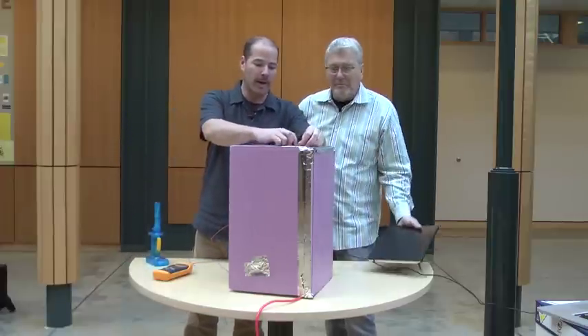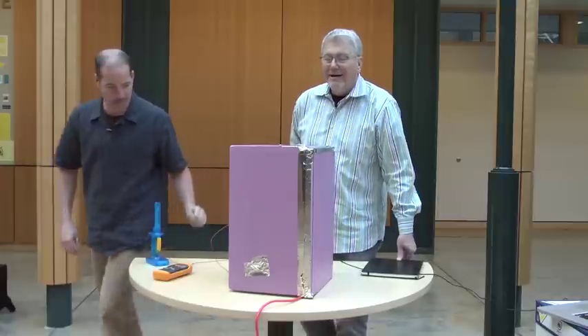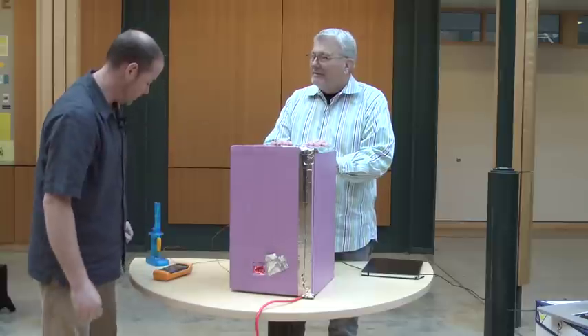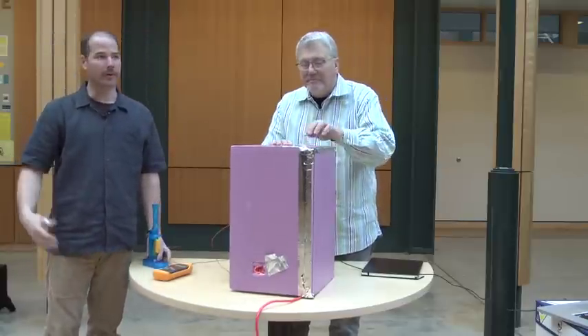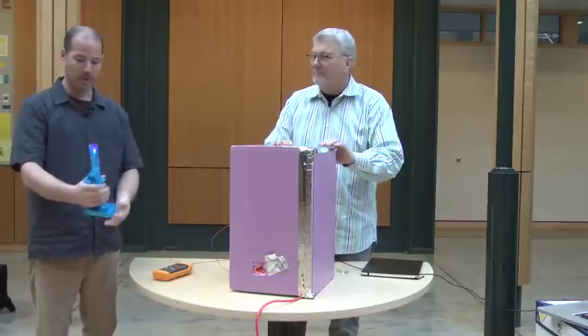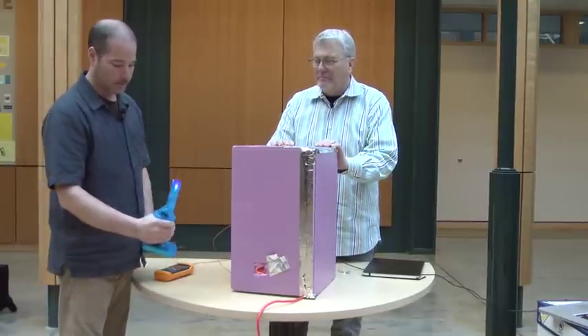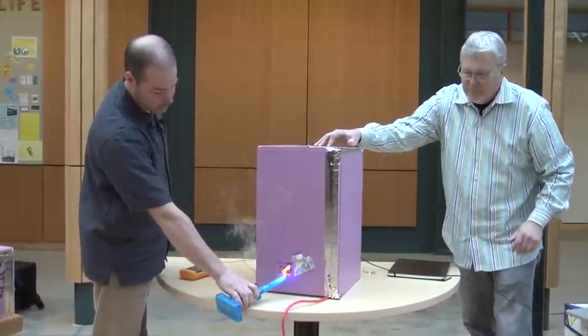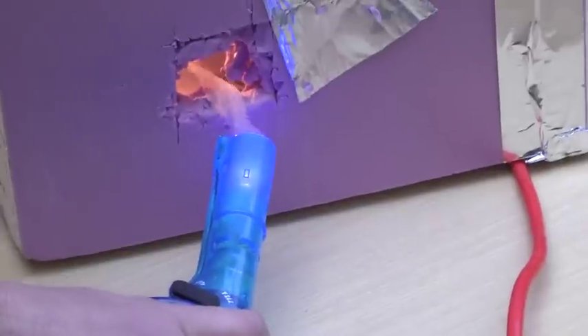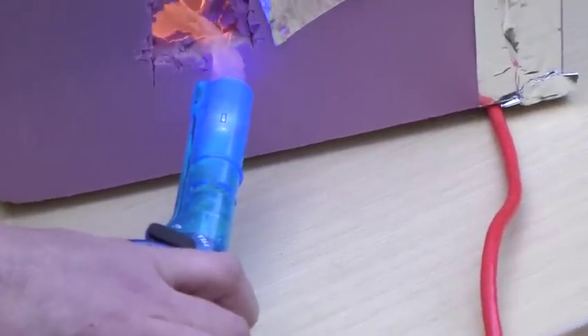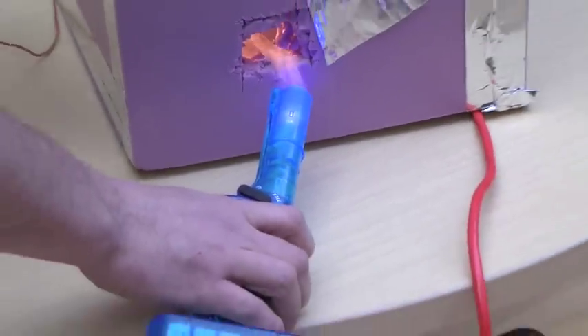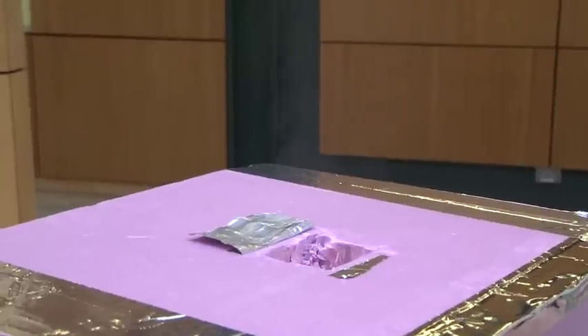So we've got a little hole in our attic where somebody installed one of those nice recessed cans, but it wasn't airtight. And we've probably got some holes around the bottom of our home where we have utilities coming in and things like that. So this is just a smoke generator, and all we do is get it warmed up, and we can watch the air leakage that's being drawn in through the stack effect, essentially. And you can see how essentially we have air moving through our assembly because of the warmer indoor temperature and the colder outdoor temperature. And that air is drawn in through the assembly and then exits through the top of the assembly.